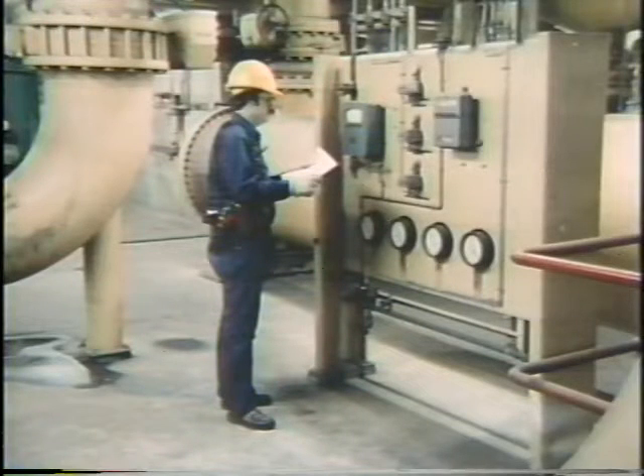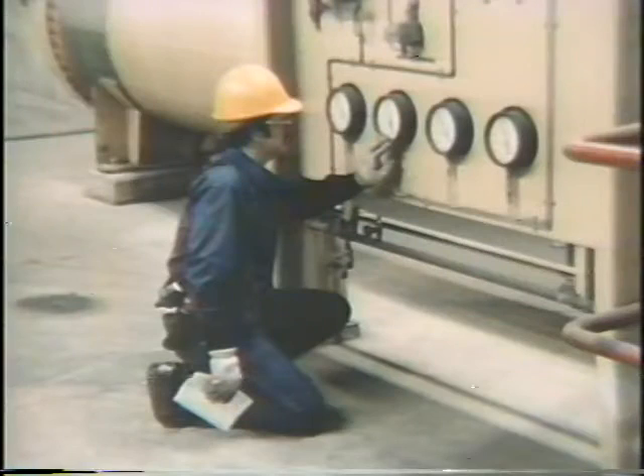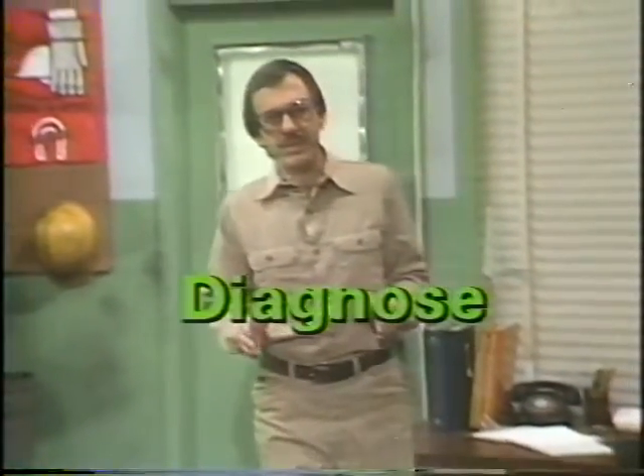And sometimes you'll be able to recognize the problem while you're looking for symptoms, but other times you won't until after you've finished observing all of the indications and have analyzed the symptoms together. If there are any indications in the field, don't forget to observe those as well. See what kind of indications you come up with there and compare them with the indications you have observed on the control panel.